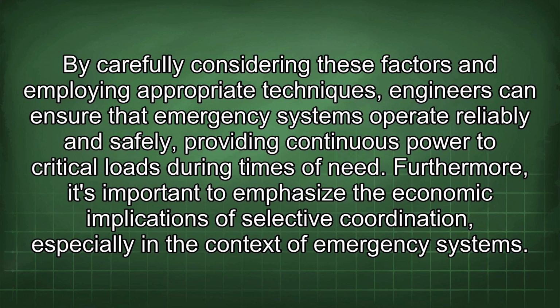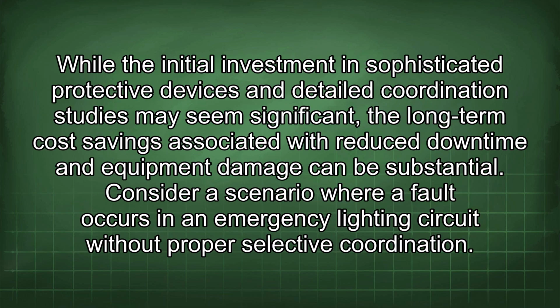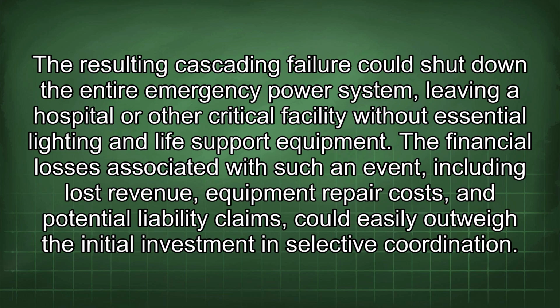Furthermore, it's important to emphasize the economic implications of selective coordination, especially in the context of emergency systems. While the initial investment in sophisticated protective devices and detailed coordination studies may seem significant, the long-term cost savings associated with reduced downtime and equipment damage can be substantial. Consider a scenario where a fault occurs in an emergency lighting circuit without proper selective coordination. The resulting cascading failure could shut down the entire emergency power system, leaving a hospital or other critical facility without essential lighting and life support equipment. The financial losses associated with such an event, including lost revenue, equipment repair costs, and potential liability claims, could easily outweigh the initial investment in selective coordination.